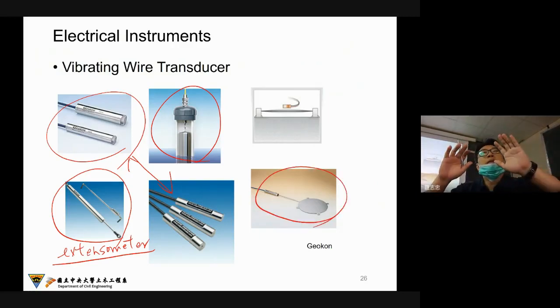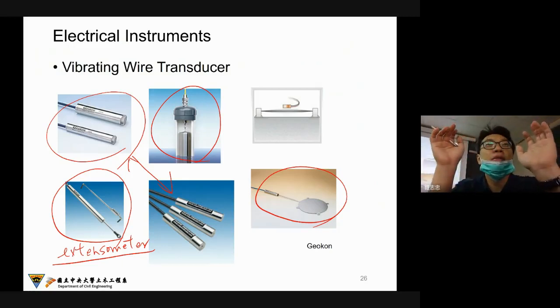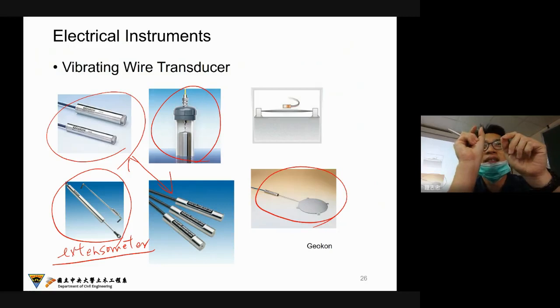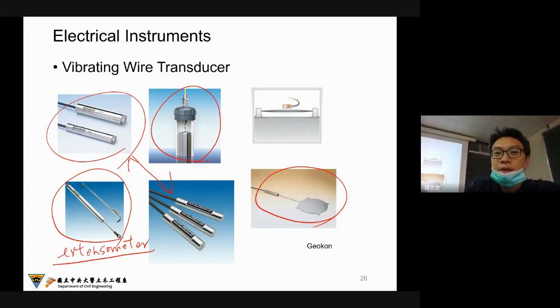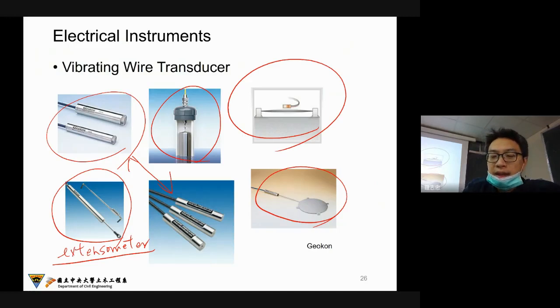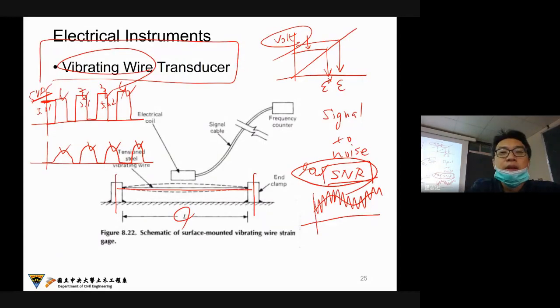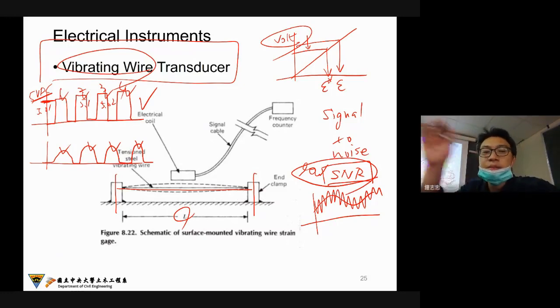So based on the strain gauge, we can change the core of the strain gauge to a vibrating wire transducer, and with this we get the advantage, as I said, we can just count the steps of the signal without any quantification of the voltage, so I can easily check the displacement, the strain, or the pressure.